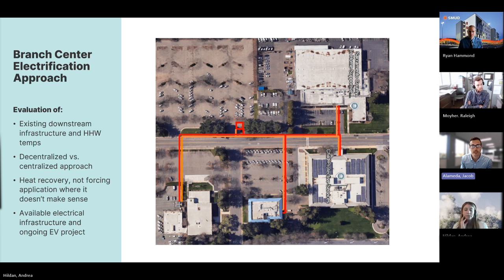So the only coils in piping at those buildings are the coils in those air handling units. So really, you're not having to change all the infrastructure that you would in a typical VAV with hot water reheat system, where the piping is going to all your reheat coils, and you have to change every reheat coil, all the piping to all those reheat coils. So in these ones, it was just really the main air handling units at those buildings.